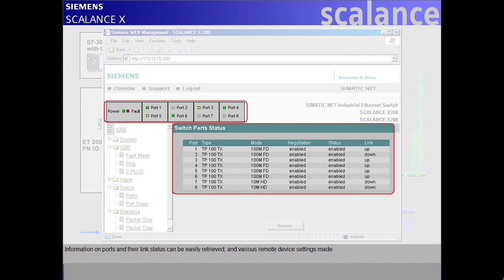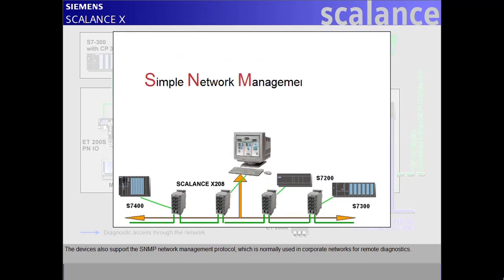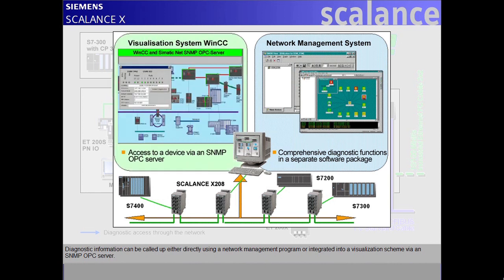Information on ports and their link status can be easily retrieved and various remote device settings made. The devices also support the SNMP network management protocol, which is normally used in corporate networks for remote diagnostics. Diagnostic information can be called up either directly using a network management program or integrated into a visualization scheme via an SNMP OPC server.